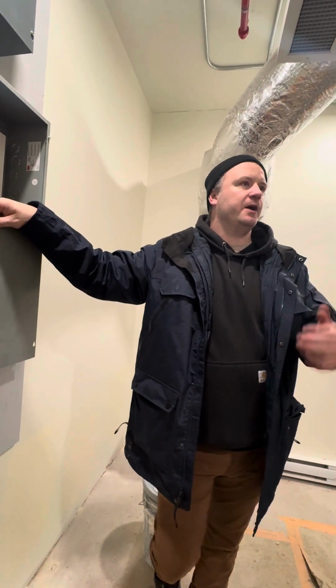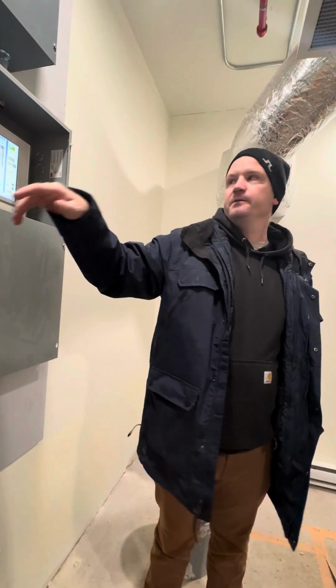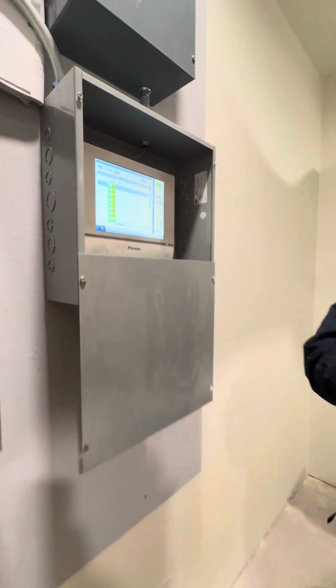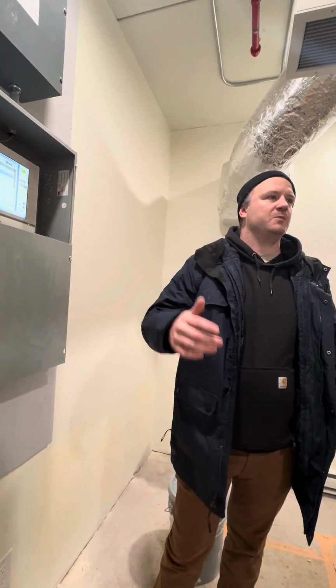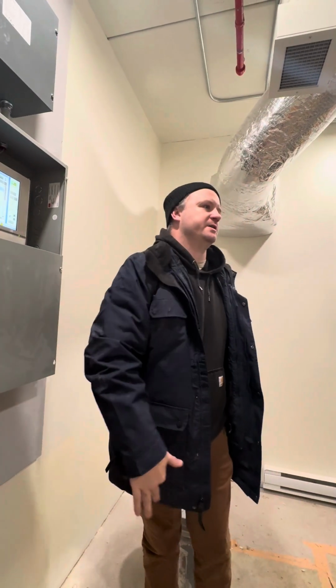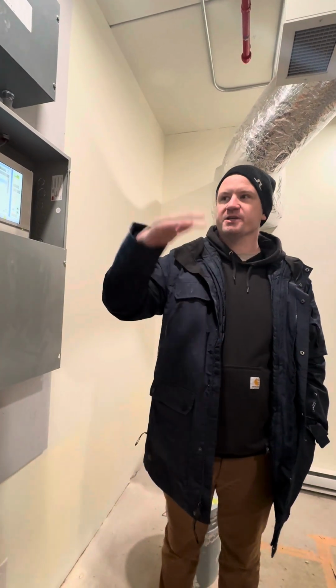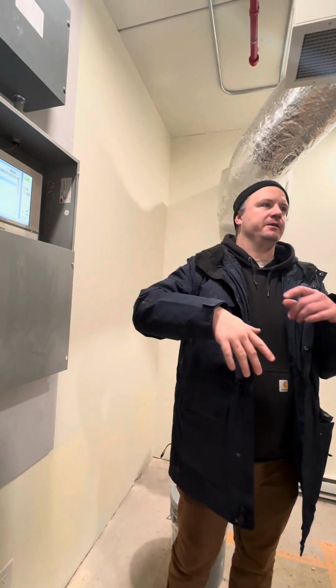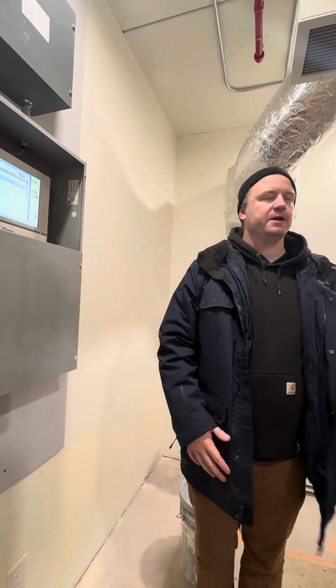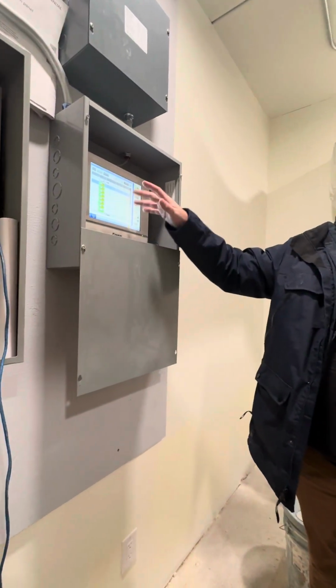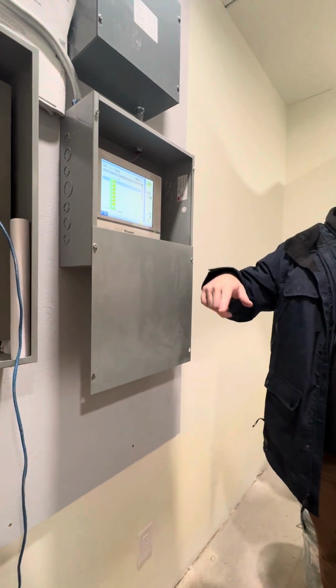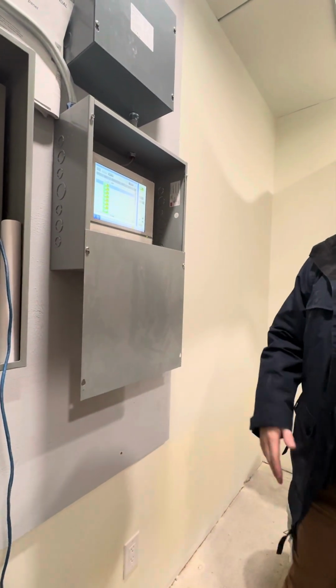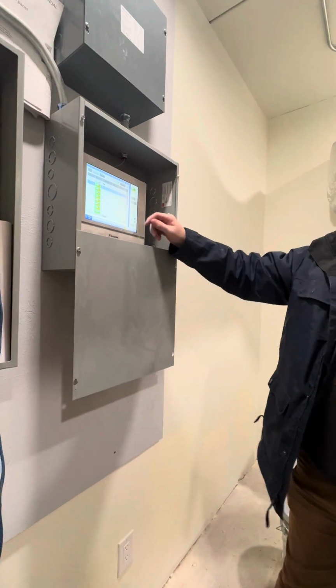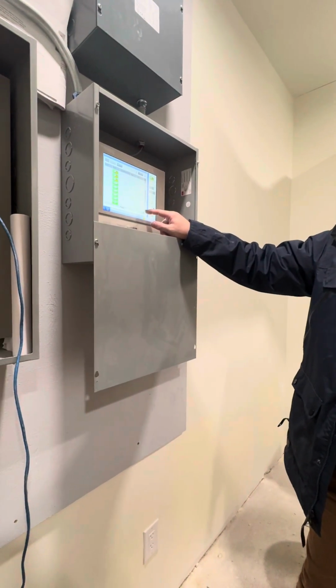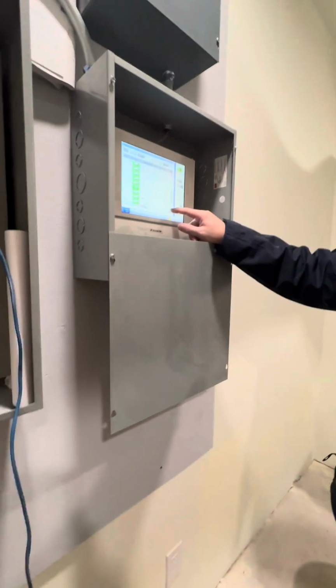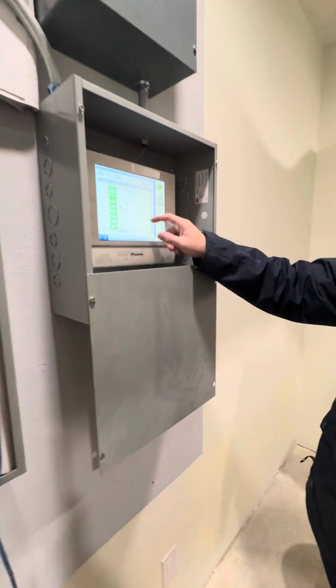So if you find that all of the breakers are on and these don't go away, send us an email, and we'll come do that procedure where we shut all the fan coils down, shut the outside unit off, and turn them all back on. Sometimes it gets stuck in this mode, even if you put the breaker off and then back on. Sometimes it just takes a full reset, which is likely what is happening here. So your other system is good, all green, good to go.